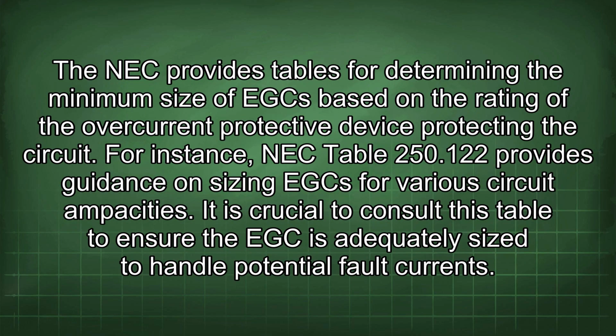The NEC provides tables for determining the minimum size of EGC based on the rating of the overcurrent protective device protecting the circuit. For instance, NEC Table 250.122 provides guidance on sizing EGCs for various circuit ampacities. It is crucial to consult this table to ensure the EGC is adequately sized to handle potential fault currents.